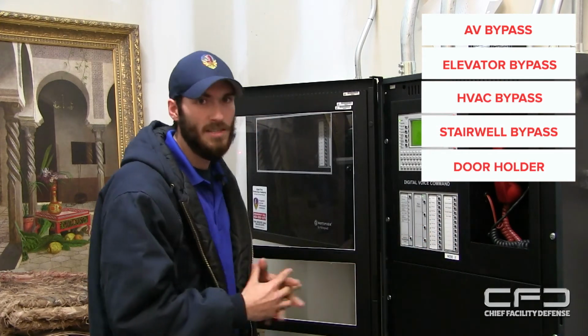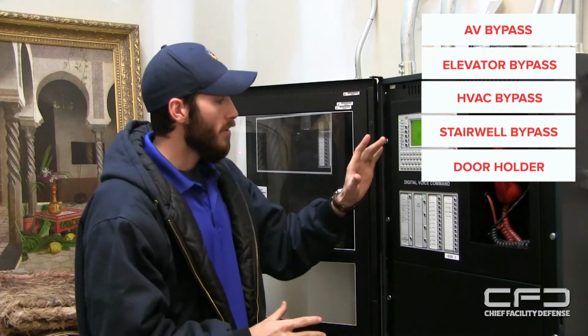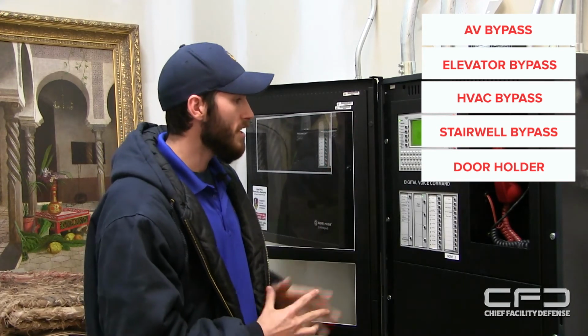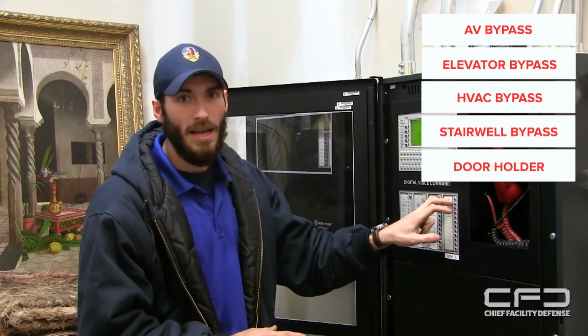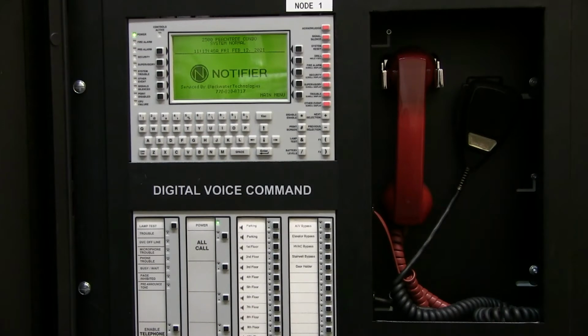The door holder is a bypass, so whenever you are doing this, most of the time you will only need to use the AV bypass, and that stands for audio visual bypass. So if you do not want the horns and strobes going off, you will need to call ahead to our monitoring station, let them know how long you need to put the system in test, and go ahead and bypass whichever ones of the key buttons that you will need to use.